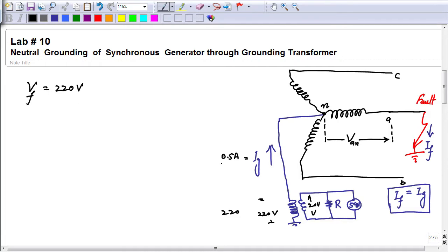We want a current of 0.5 ampere in the neutral circuit against this voltage. How much should be the impedance in this path? That is the resistance on the primary side of this transformer, or you can say if we directly insert that resistance between neutral and ground, it will be equal to VF over the ground current IF. So that is equal to 220 over 0.5, which becomes 440 ohm. 440 ohm must be inserted between neutral and ground.